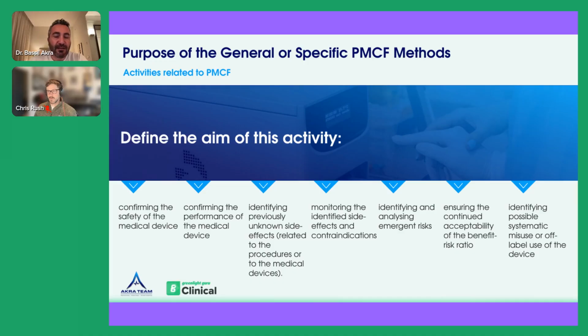Even if you use a catheter which is just in the patient for 30 minutes, that 30 minutes might give you the direct effect of the catheter. You can find the performance, but if you want to look at the safety of that catheter, you might need to monitor it longer term, because you might create damage to the patient which you cannot see immediately. Therefore, you need to confirm that it was safe in the longer term. And the PMCF is a small piece of the post-market surveillance, but it's not focusing on high-level information. It's specific to clinical information.